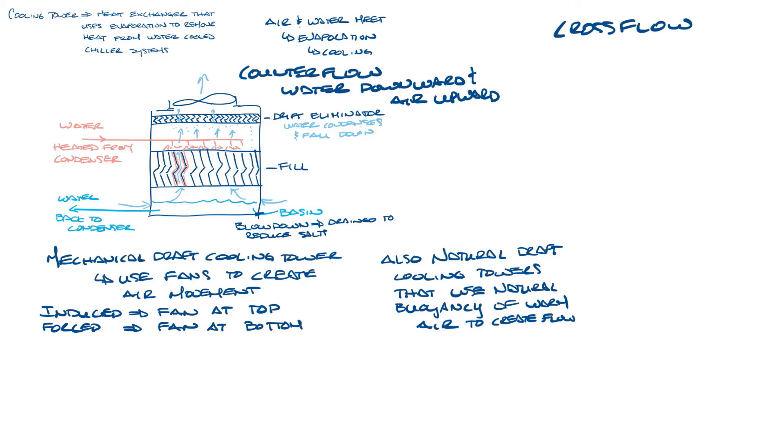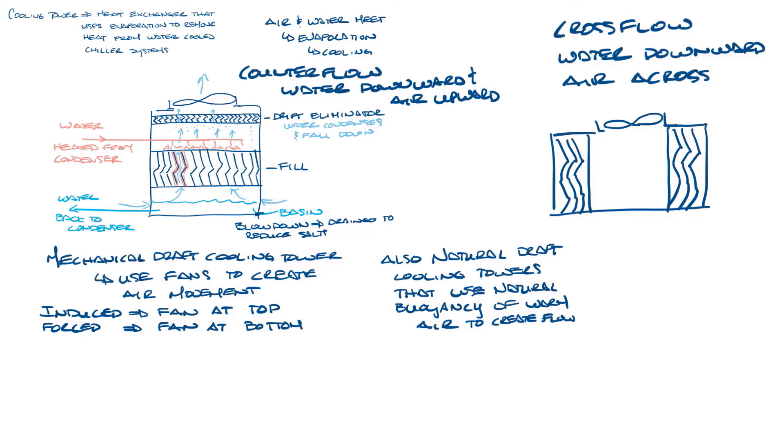In a cross flow cooling tower the water still moves downward but the air flows across it horizontally. So let me draw that here. We'll put our fan on top and then the fill will be on either side, so the water will come in at the top from the condenser, go down the fill just like in the counter flow tower, but the air flow will come in from the side on either side of this cooling tower, go across the fill, and then up out the fan. And then also at the bottom here you'll still have the basin and the water returns back to the condenser from there.